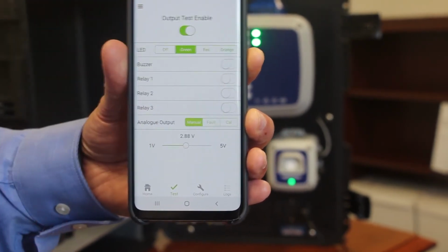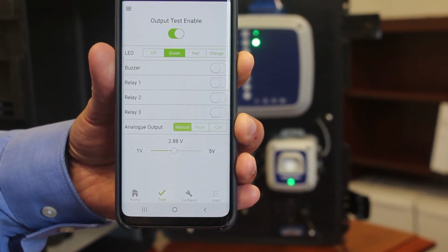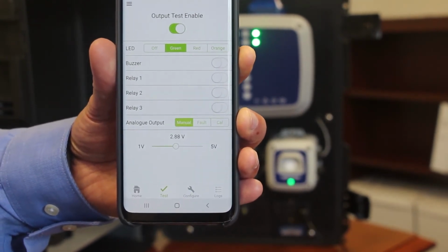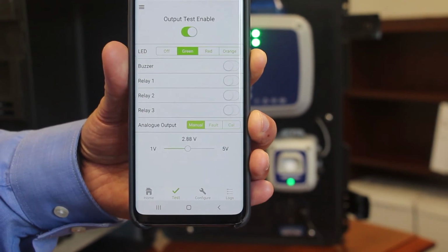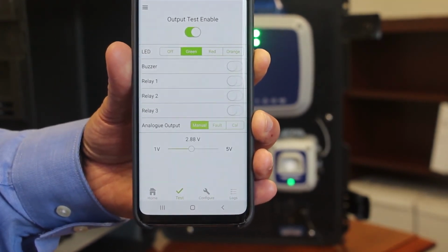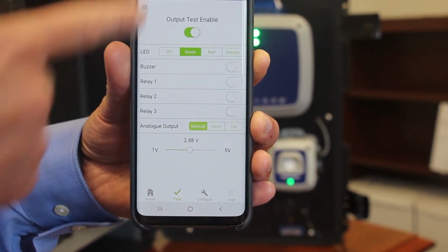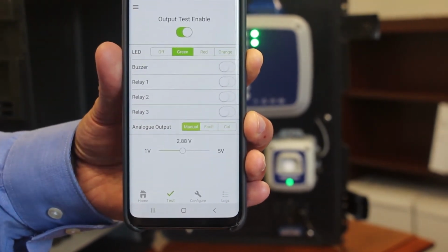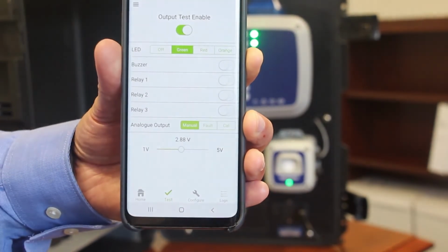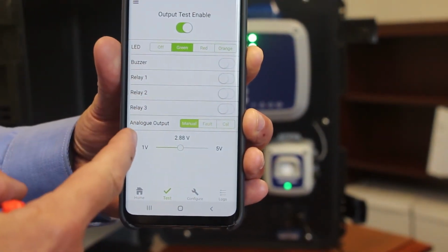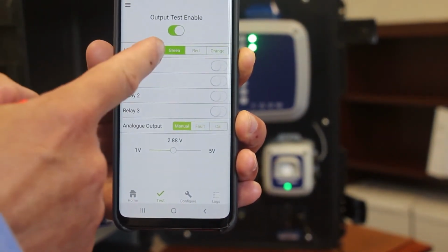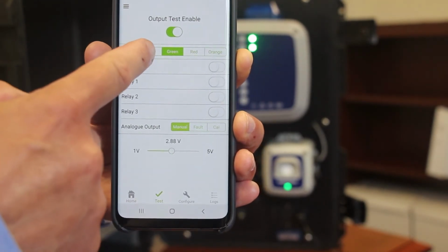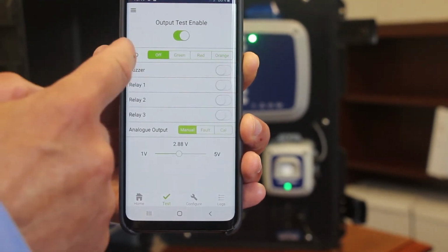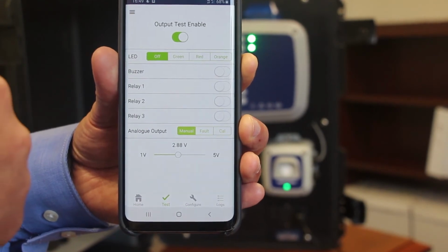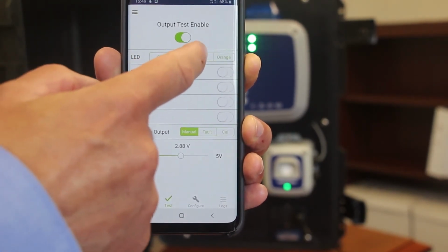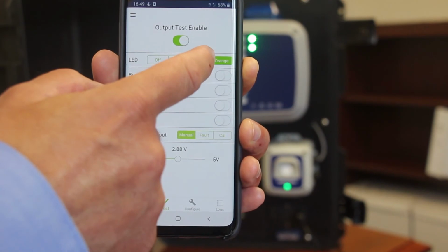When you switch this into the output test mode, on the MGS-400 controller, the detector that you have connected will actually show as offline on the controller. That's deliberate, just to make sure that when you're carrying out these tests, it doesn't interfere with the controller. So as you can see, we have a number of different options here. We have an LED test button, so you can flick through from switching the LED on the 450 detector to off. You can cycle through green, red, and orange.